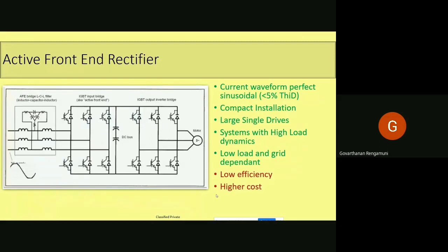The third method to meet IEEE 519 is active front-end rectifier. Active front-end rectifier. Till now, whatever you have seen is a diode front-end rectifier. Here you can see an IGBT front-end rectifier. It looks like an inverter, a VSI inverter, at the input side also, with some LCL filter at the front end.